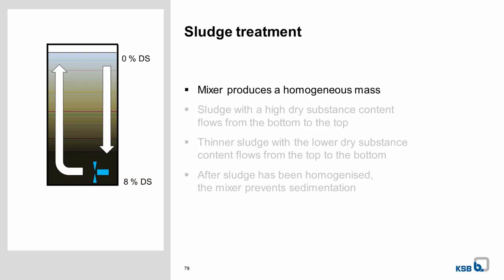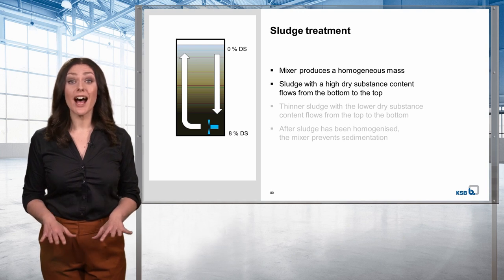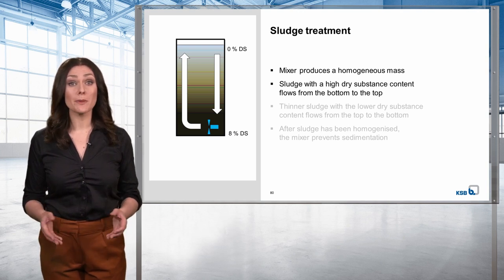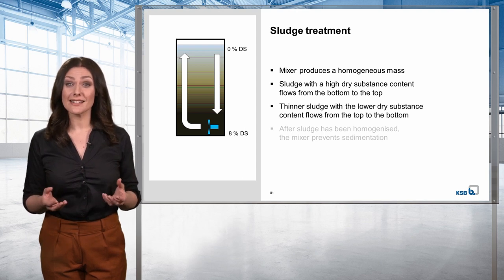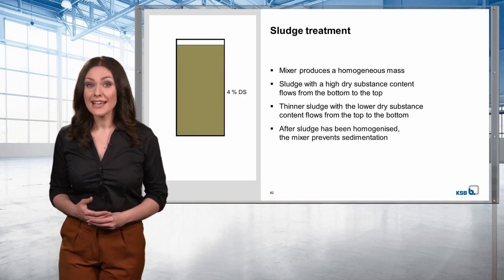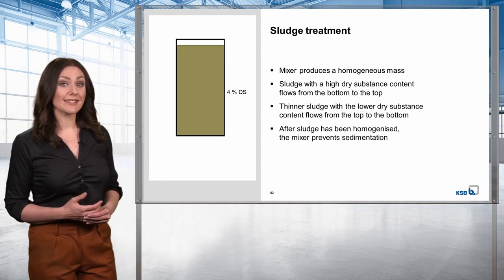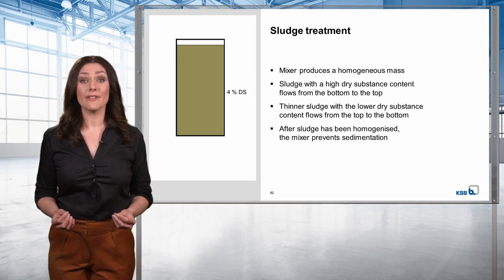This is where the mixer comes into play. Its first task is to produce a homogeneous mass. As the mixer is installed at the bottom of the tank, it moves the sludge with a high dry substance content from the bottom towards the top. At the same time, the thinner sludge with the lower DS content flows from the top to the bottom. When the mixer is started, it creates a homogeneous sludge with a DS content of 4%. After the sludge has been homogenized, the mixer prevents sedimentation.